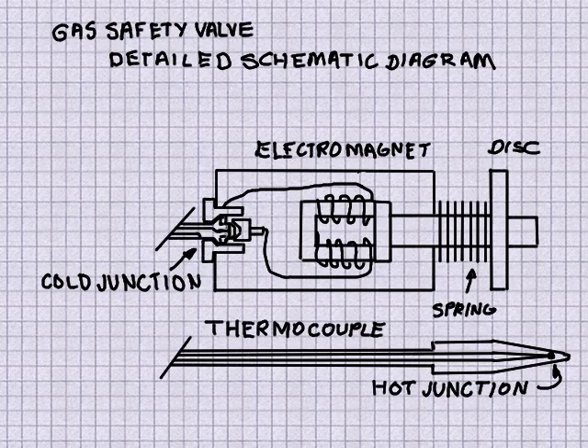Analyzing the system schematic in more detail reveals that the thermocouple itself could be causing the problem, or perhaps the electromagnet, or even a mechanical failure. Right from the start I noticed that the thermocouple cold junction, that is its terminal, was loose in its socket.